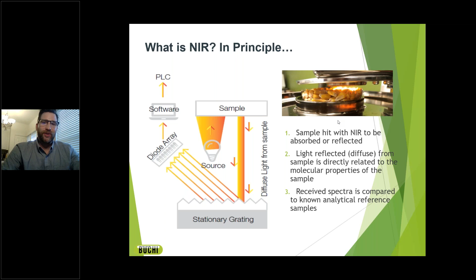So what is NIR then, the principle? Some basics about the NIR principle can be simple. Light hits the sample and light is reflected, is measured. If you want to get real nerdy with me, then a more in-depth answer would be the incandescent light hits the sample, diffuses, reflects light, which bounces off a stationary grating, and then the intensity is recorded by a DAD, or a diode array detector. Through calibration, the spectral data is quantified and predicted properties are displayed on the monitor. So in general, it's a little bit easier to say light hits the sample and light reflected is measured.